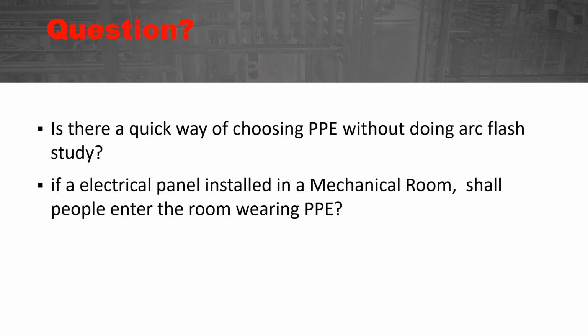Otherwise, if you're getting into this equipment, even if it is shut off, you have to treat it as energized until you have proven it and established and verified that it is electrically safe. You have to wear shock PPE, you have to wear arc flash PPE.